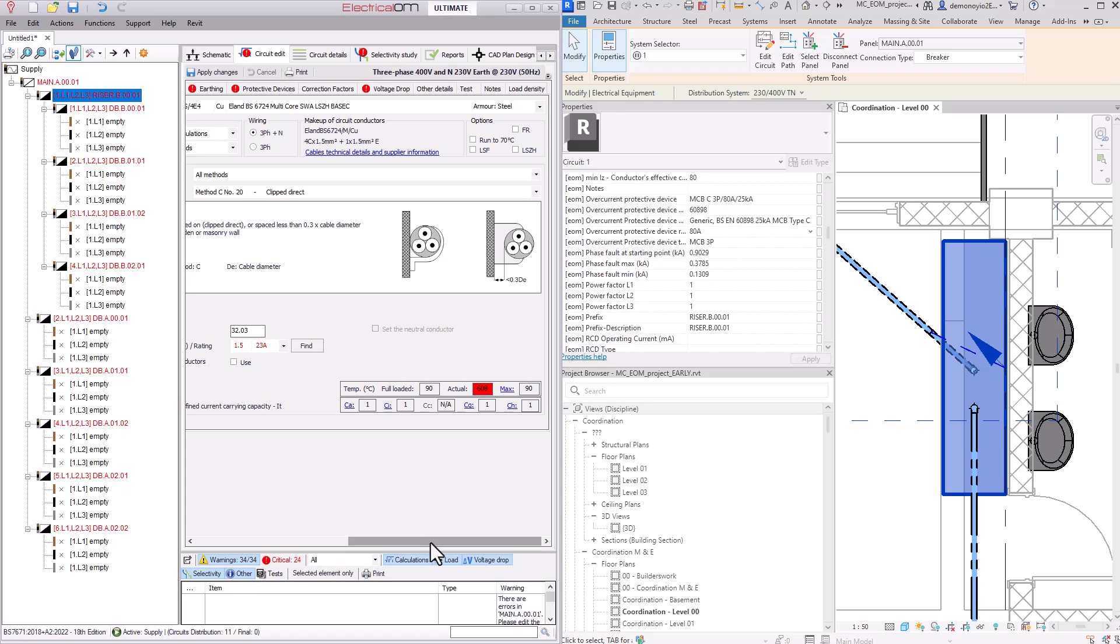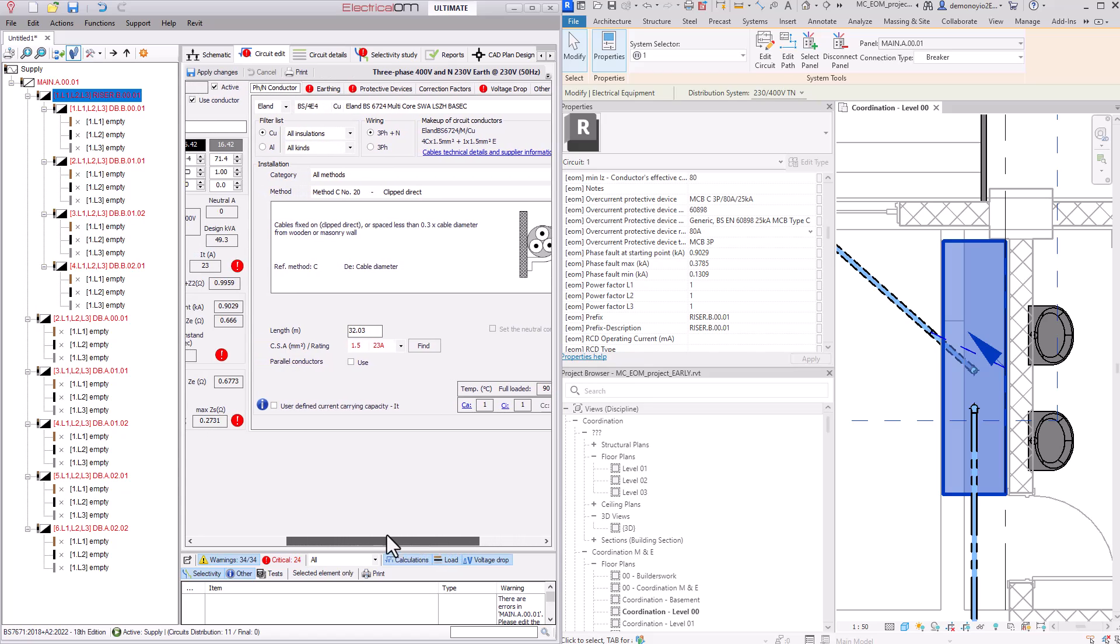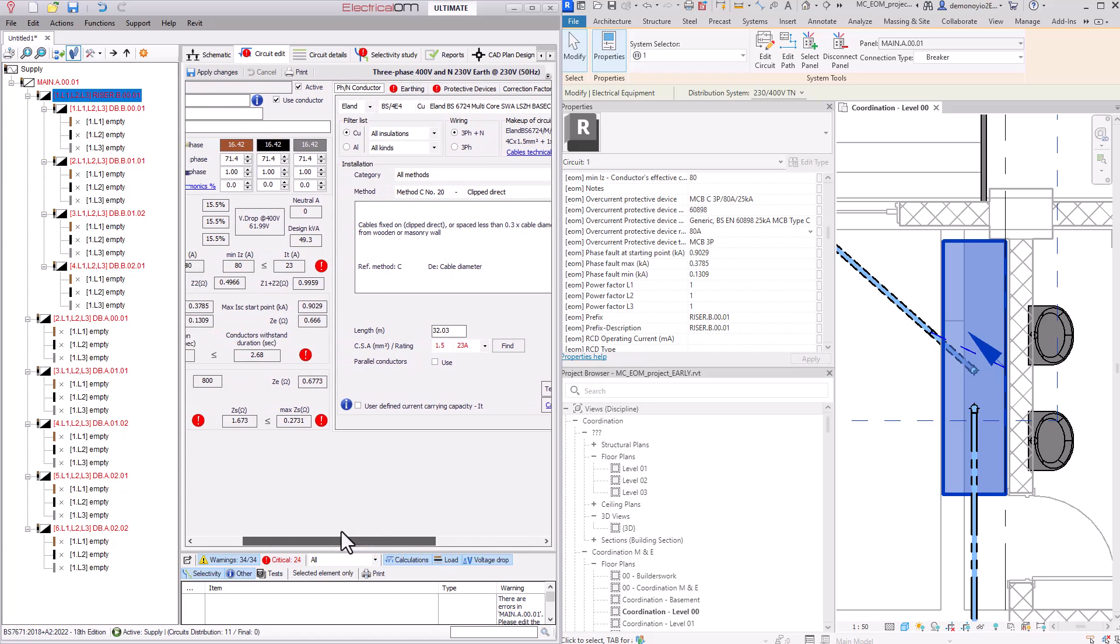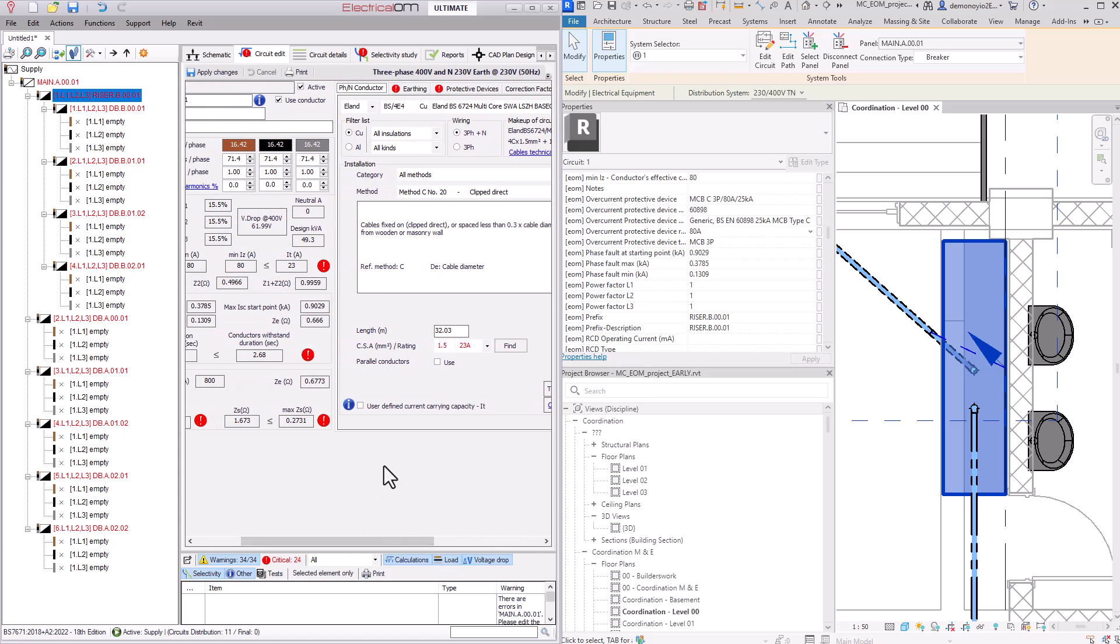We can now see various issues related to the current selections within the Revit model. Here we have variations in cable sizing and things like earthing which currently do not comply with the regulations. We are now going to make some changes here and apply the detail directly into our MagiCAD model.